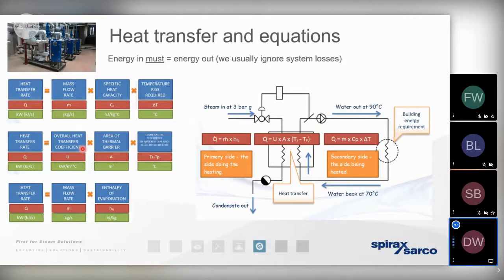But if we're going back to first principles to size a totally new application, then we can do it by means of calculation. And we then multiply that by the temperature difference between the steam on the primary side, which, remember, we can use the steam tables to denote the steam temperature by having an understanding of the pressure, and then we subtract from that the average temperature of the process being heated. So in the case of the equation we're looking at here, the average temperature of the process is going to be 80 degrees. So by multiplying the U value by the A value by the temperature difference, we arrive at the Q value.